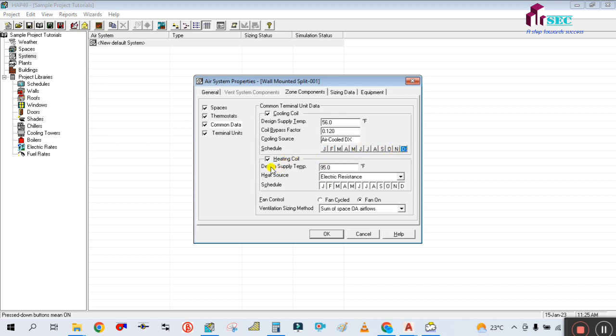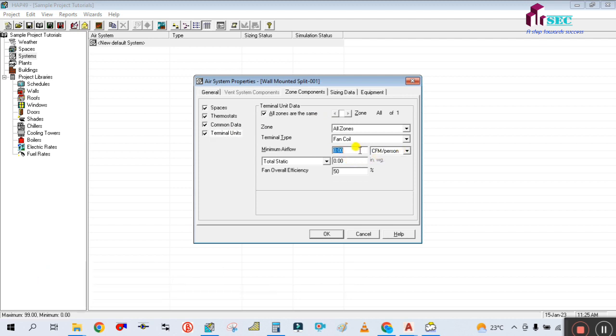Simply uncheck the Heating Coil because it is not required - heating is not needed. Then go to the Terminal Unit tab. In the Terminal Unit settings, select 20 CFM per person, and the static pressure is 0.